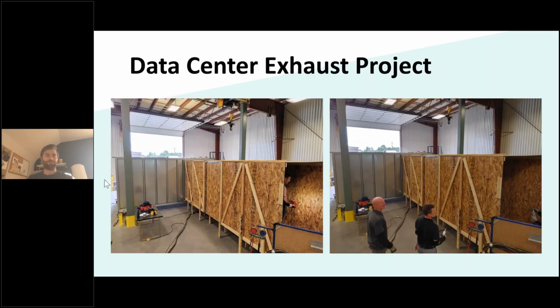In the end, we had to also test these units. So we had 3 factory test visits from the client. We had to flip the unit on its side to provide a 20-foot long duct section into the bottom of the unit. This was to get laminar flow through there and act as if it was on site. Ultimately, our goal was for 68,000 CFM at max output on the fans, and we were able to achieve 75,000 CFM. So quite a bit of a boost, and for the number of units that this client will have, marginal gains are huge in the end. So they were very happy with that.